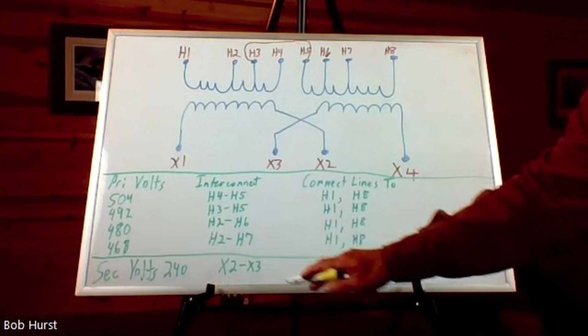Okay, and then that ratio right there, we go in here and look at our secondary. It says interconnect X2 to X3. So X2 to X3, we're going to tie those two wires together right there, whether it be with a jumper or a wire nut, however it's going to be.